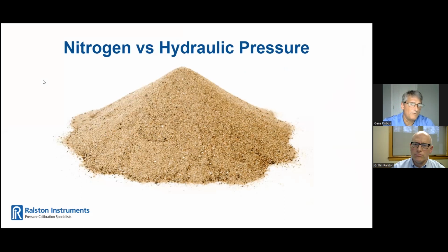Hydraulic pressure is like pouring sand loosely on a flat scale when used as a source of pressure. The sand will provide some initially, but runs off the edges, causing the pressure to drop, and more sand is needed. So you have to consistently add or remove sand to keep it steady. But a manual nitrogen pressure controller simply dials in the pressure you need with extreme precision. It's like adding a precise amount of sand in a container with no grains falling off or needing to be adjusted later.